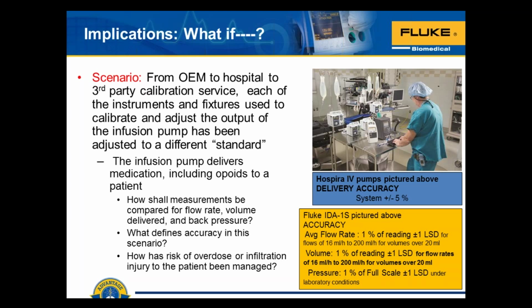But all of these have to take into account those uncertainties or variables that you need to control when you're making your own measurements on the infusion device itself. So the what-if is, what if we were inaccurate enough that the medical device, and its uncertainty, put it just on the upper edge of the high side of its volume delivery specification, and our test instrument was also on its upper limit of that same unit of measure for volume.